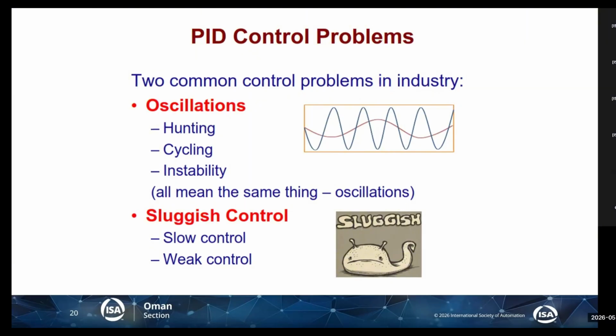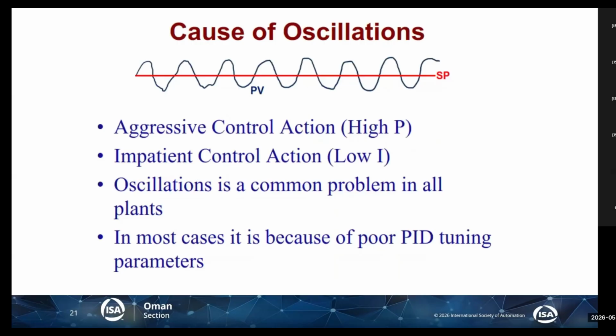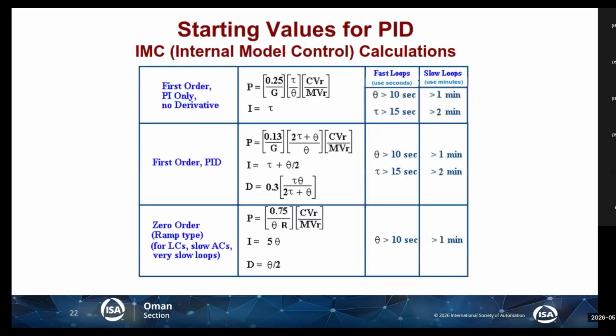So we have to investigate, sit with the operators, speak to them, and try to understand whether this is a controller action or another action, because other issues you cannot solve with tuning. Tuning is only for bad performance of the controller, not to solve valve issues or instrumentation issues. So I think this is already explained, causes of oscillations. Then, one of the tuning methods.